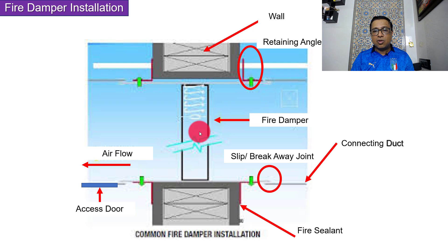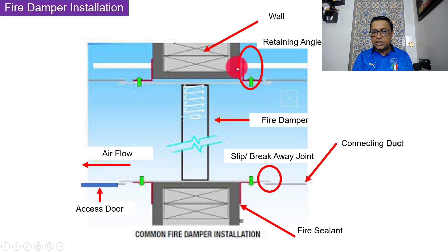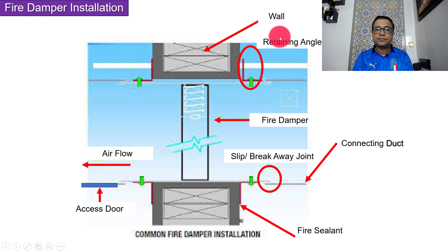The third important point is how the sleeve and the wall are properly joined. There is always a retaining angle sitting along the wall. The vertical part of the retaining angle is riveted to the sleeve, while the horizontal part acts as a stopper. This happens on all four sides. You can see here — this is the retaining angle and this is how it has to be installed.